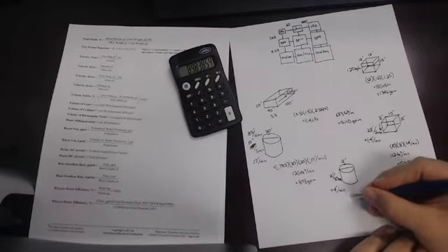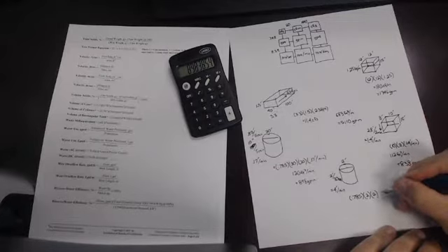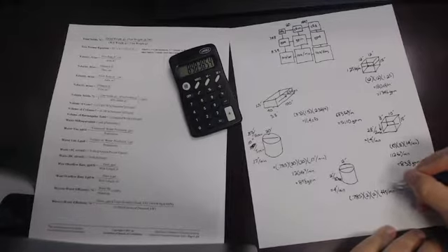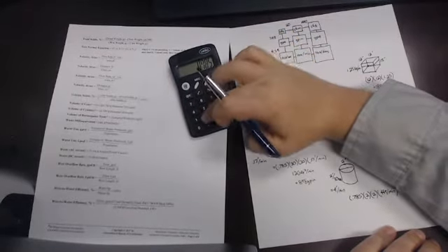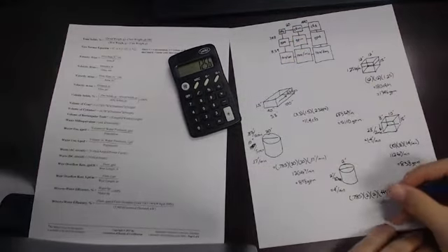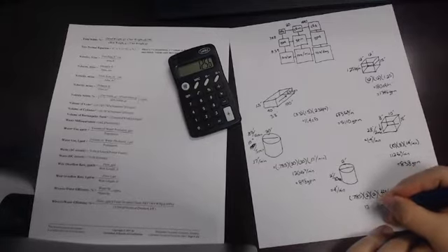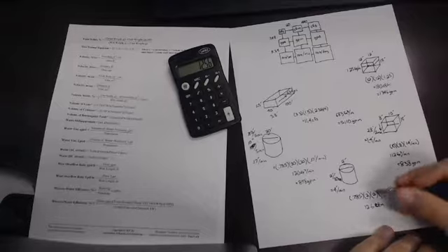So we'll take 0.785, because it's a cylinder, times 2 foot times 2 foot times 4 feet, so we're at feet now, per minute. You get 0.785 times 2 times 2 times 4, and we'll round up to 12.6 cubic foot per minute, CFM.